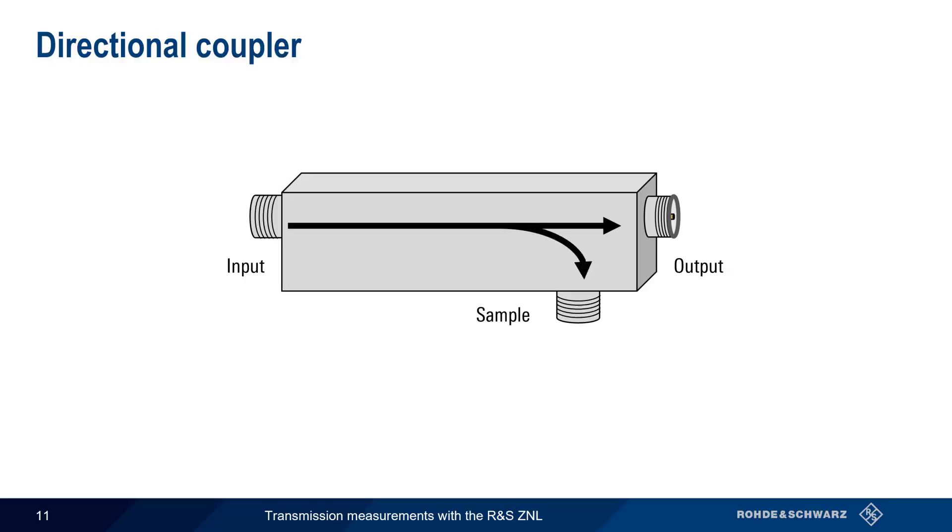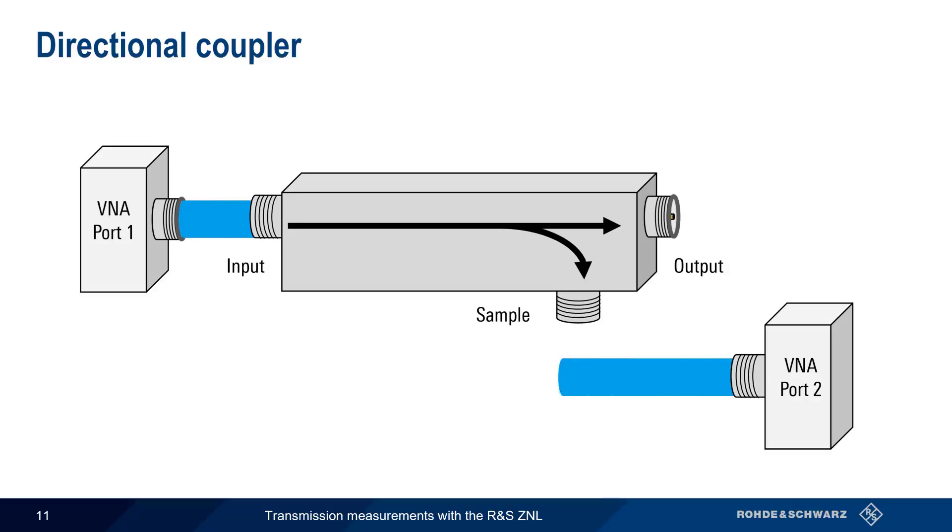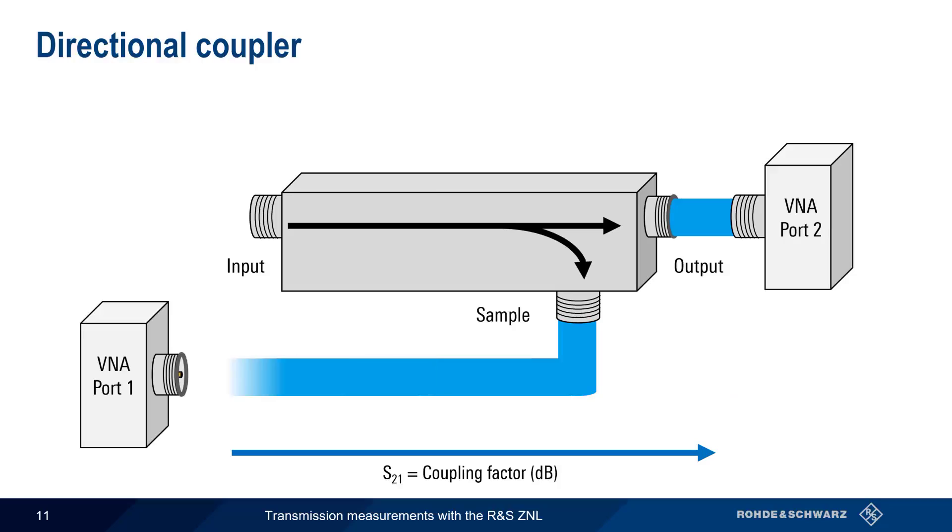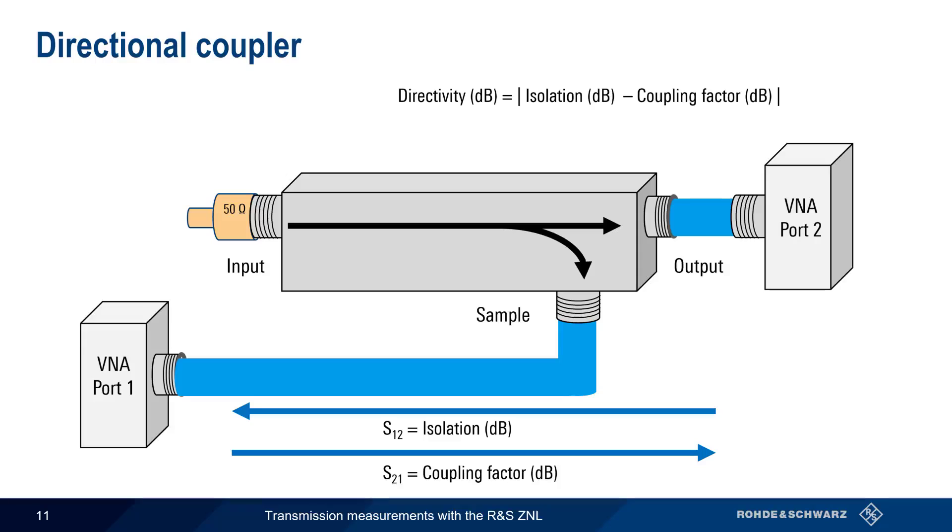In addition to passing power from the input to the output, some of the power is also routed to the sample port. We can verify and measure the function of this coupler in two steps. First, we stimulate the input port and measure at the sample port. This gives us the coupling factor. We then make another measurement, this time stimulating the output port and then measuring at the sample port. This is called the isolation. Directivity is then calculated by the difference between the coupling coefficient and the isolation value. Note that in both steps we've terminated the unused port. This is good practice whenever using a VNA.